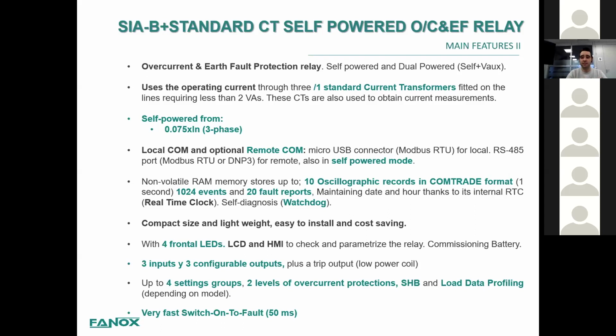In this case, in terms of the front of the relay, we have four frontal LEDs with LCD and the HMI to check and parameterize the relay, and also a commissioning battery. In this case, we have 3 inputs and 3 configurable outputs, plus the trip output for the low power coil. In the same way as the previous one, we have up to 4 setting groups, 2 levels of current protection, second harmonic blocking, and also load data profiling depending on the model.